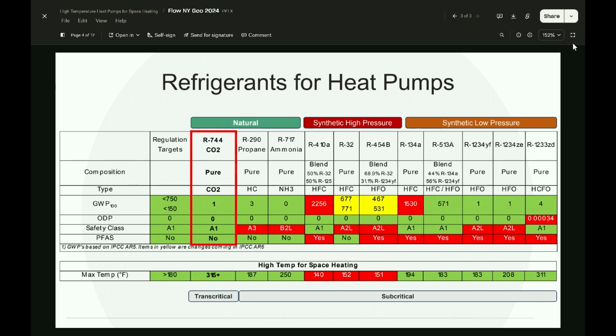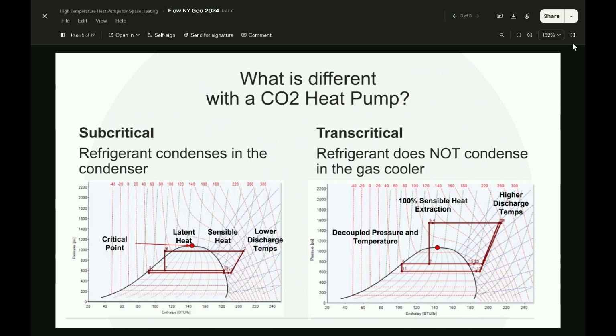So what are we actually making? We're limited further, and we've got to create something. I'm going to argue today on behalf of CO2, and that's exactly what we're building into products today. All those other refrigerants besides CO2 are subcritical — they condense and have a condenser in their system. We make a transcritical CO2 heat pump. It's a little different, but it allows us to take 100% sensible energy out of the air, and do interesting things like optimize for heating to make a really efficient high temperature heat pump.